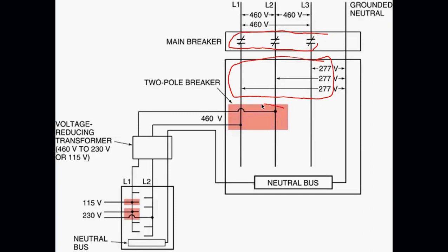We take 2 legs off of this, and we go to another transformer. It steps it down, so then we have 2 legs of pretty standard power, that starts looking more like the breaker panels you're seeing in the house, L1 and L2.